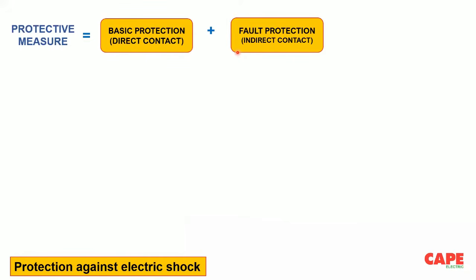Now, protection against electric shock. There are several techniques. Basically, you need to have basic protection. You need to have fault protection. Basic protective measures are there, such as live part barriers, obstacles, placing out of reach; fault protection: automatic disconnection, ELV, separation, double insulation. There are different techniques. For example, in our last webinar regarding solar PV, we discussed a lot about double insulation.